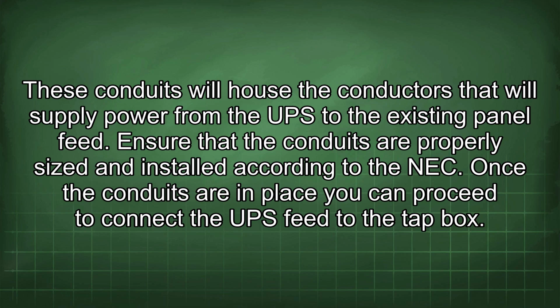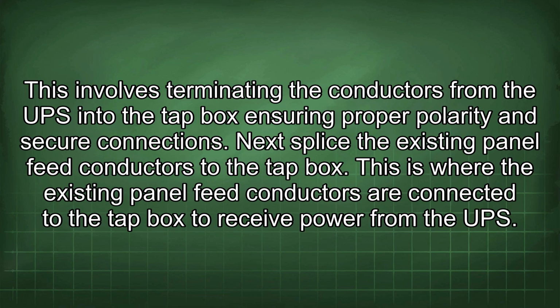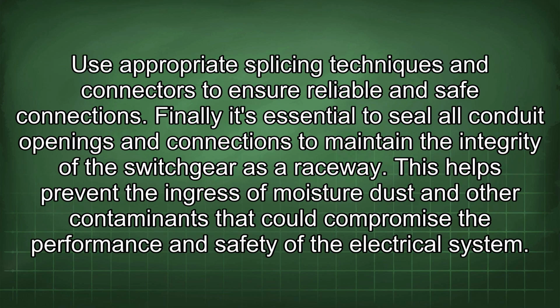Once the conduits are in place, you can proceed to connect the UPS feed to the tap box. This involves terminating the conductors from the UPS into the tap box, ensuring proper polarity and secure connections. Next, splice the existing panel feed conductors to the tap box. This is where the existing panel feed conductors are connected to the tap box to receive power from the UPS. Use appropriate splicing techniques and connectors to ensure reliable and safe connections.